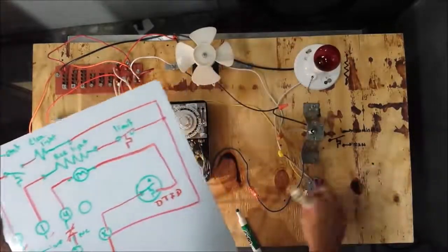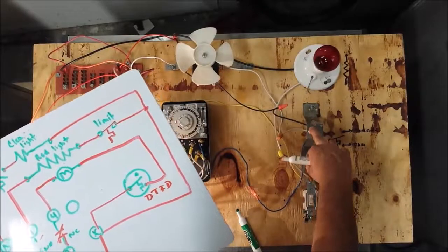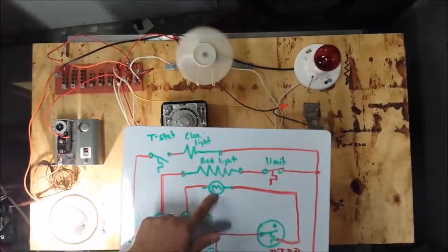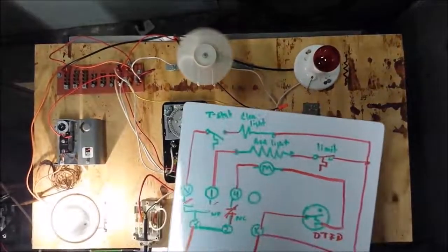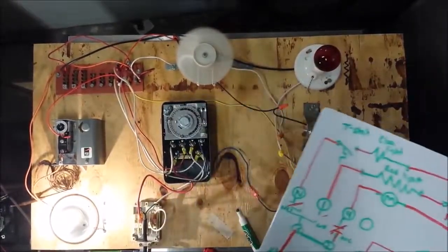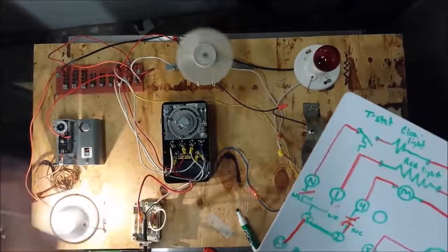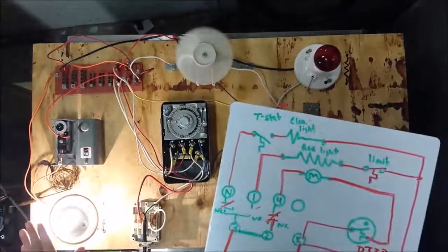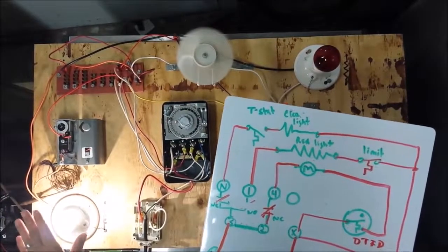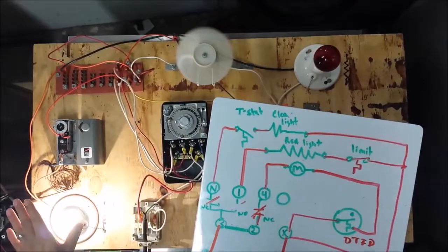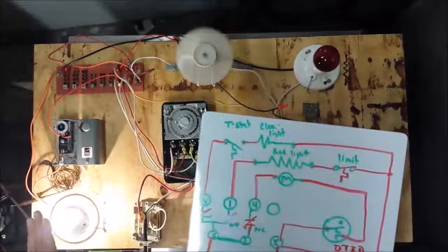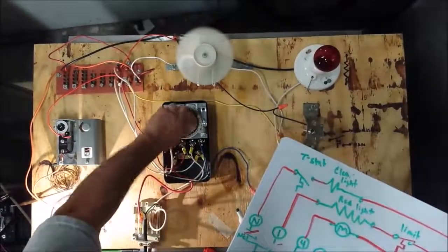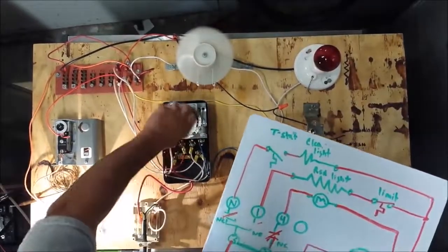So let's do that. So temperature falls, thermostat closes. And of course now our fan motor is operational. Okay? So now we're in basic refrigeration operation. Compressor, refrigeration system's running, fan motor has come on, our liquid line solenoid valve coil is energized, allowing refrigerant flow to happen. Everything's working normally. Alright, so once again, let's put this thing back into defrost.